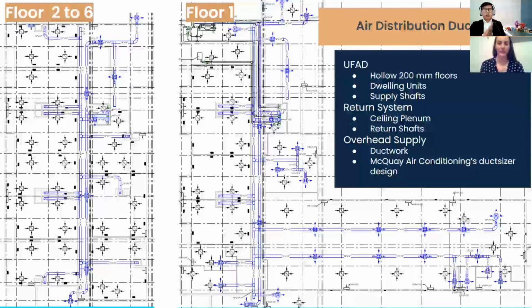Now, with regards to the actual ductwork, the entirety of the ductwork was sized using the McQuay air conditioning duct sizer design tool. And from this, we also applied the values and related aspects that would be present for a duct system, such as itself being a low pressure duct system for this multi-unit residential building. And furthermore, rectangular ductwork was chosen over round ductwork for the entirety of the system, for 2 specific reasons. The first one being that they occupy less space, therefore allowing more space in the ceiling plenum for air to circulate. And then the second one being that they are more common or better for a low pressure system, such as the one that we have here.